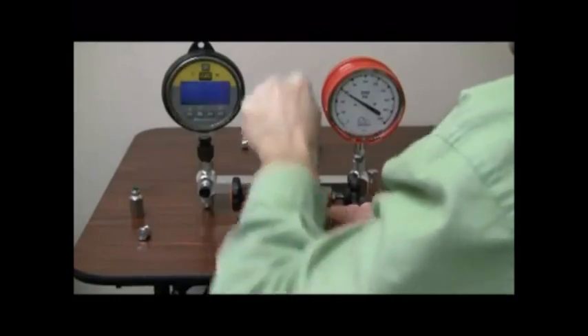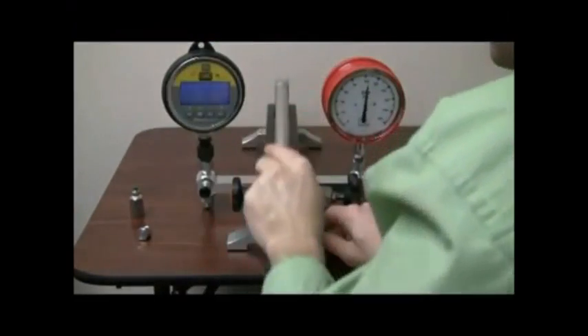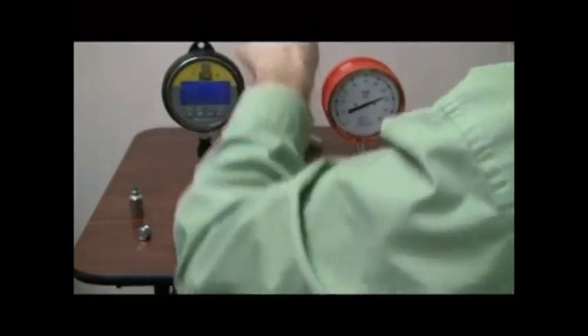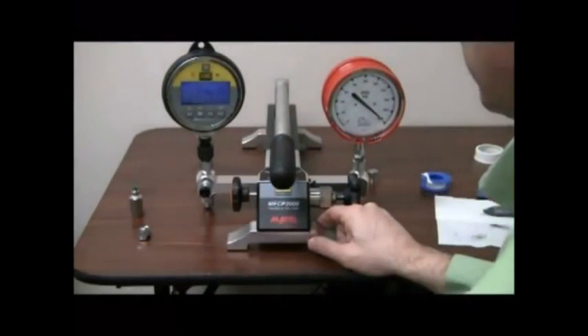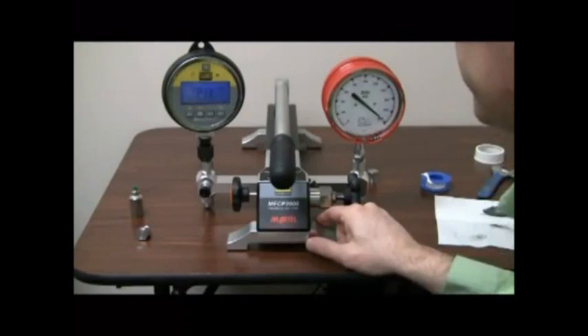Gently crank down on the handle to generate the pressure that you desire. In this test, we're going to go up to full scale, which is 200 psi. Once again, I'm checking for leaks, making sure everything's tight. Now it will take some time to settle, but as you see here, we will not have any leaks present.